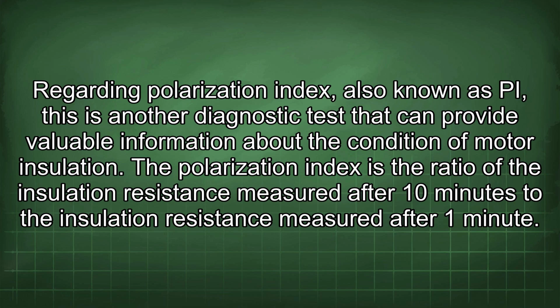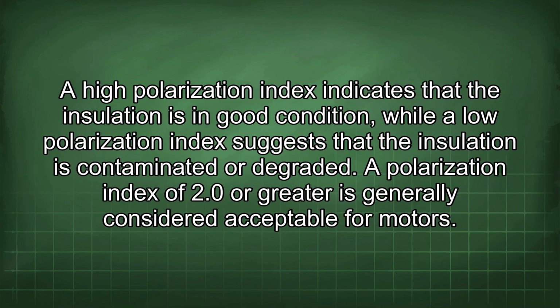Regarding polarization index, also known as PI, this is another diagnostic test that can provide valuable information about the condition of motor insulation. The polarization index is the ratio of the insulation resistance measured after 10 minutes to the insulation resistance measured after 1 minute. A high polarization index indicates that the insulation is in good condition, while a low polarization index suggests that the insulation is contaminated or degraded. A polarization index of 2.0 or greater is generally considered acceptable for motors.